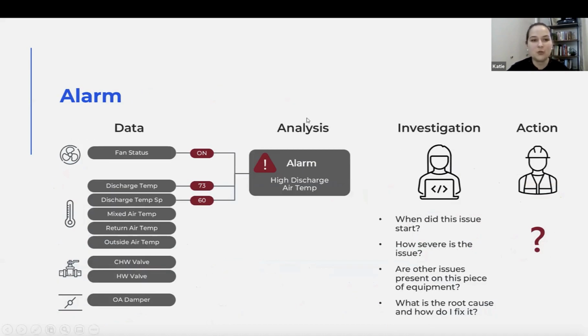All right, so we're going to do a deeper dive into the difference between an alarm and a fault, because I get this question a lot. Iowa would talk about this frequently. An alarm, here's an example: you have an air handler again, and your alarm is looking for a high discharge air temp. If you saw an alarm come in as a technician, it just says high discharge air temp. When you get that alarm, you don't know when it started, how severe it is, if anything else is impacted, what the root cause is, or how to fix it. You have to search that out and do the investigation before you take action.